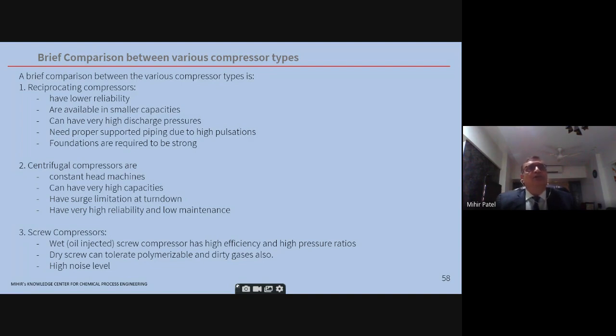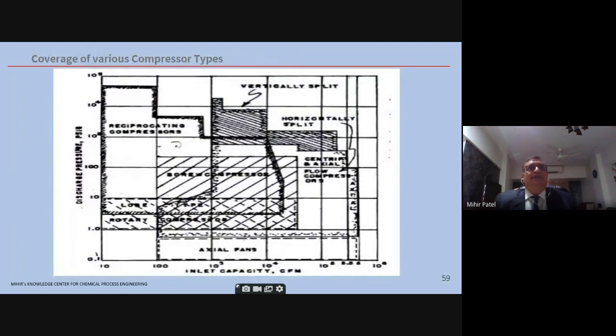And screw compressors. Now wet screw compressors have very high efficiency and very high pressure ratios. Normally an oil-free screw compressor may have a pressure ratio of 1:3, 1:4. Oil injected, because the oil acts as a cooling medium, you can go up to 1:23 pressure ratio. Okay, however the oil is there on the discharge, so you have to be careful. You have to have special filters on the discharge. The dry screw can tolerate polymerizable and dirty gases also. Okay, this is very important for the screw compressor. The coverage of the various types, as you can see: on the smaller capacity on the left is the reciprocating type. On the right hand side are the axial type for very high capacities.